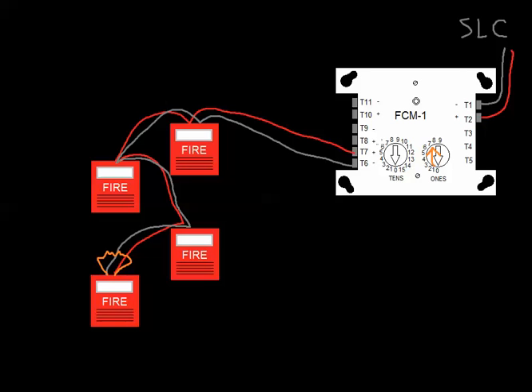But basically, the current that's flowing through that circuit in a normal state, when that control module is not turned on, would be coming from the SLC. Once something in the program tells it to turn on, this is an output. So once an input turns on that is mapped to this device, now it's going to pass whatever the input power to this control module is. So in this case, if these are horn strobes, it's just going to be some sort of 24-volt power.